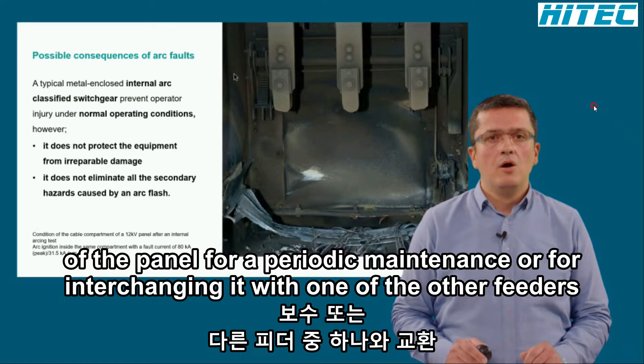Coming back to the definition of normal operating conditions, this is not always in line with the necessities of real life. Just imagine a simple maneuver when a high voltage door is opened to take the circuit breaker out of the panel for periodic maintenance or for interchanging it with one of the other feeders. As expected, the bus bar should remain live. This is what an LSC2 type service continuity category offers. So what about the safety in such status?